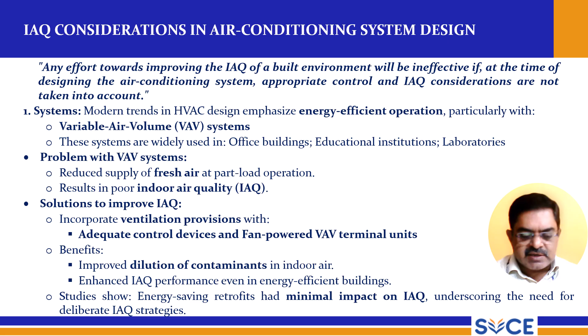Modern trends in HVAC design emphasize energy efficient operation, particularly with variable air volume VAV systems. These systems are widely used in office buildings, educational institutions, laboratories. The problem with VAV systems is that reduced supply of fresh air at part load operation results in poor indoor air quality, that is IAQ. Solutions to improve IAQ: incorporate ventilation provisions with adequate control devices and fan powered VAV terminal units. Benefits are improved dilution of contaminants in indoor air, and enhanced IAQ performance even in energy efficient buildings. Studies show energy saving retrofits had minimal impact on IAQ, underscoring the need for deliberate IAQ strategies.